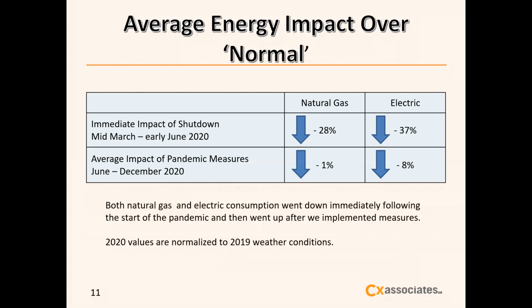I do want to caution us here. The very low energy impact of the measures we implemented for COVID are due to the changes we made and the low occupancy and the lack of events. If we maintain these pandemic sequences when we go back to our much anticipated operating mode of full occupancy and music and plays and weddings, etc., the energy impacts of maintaining the set points of doubled outside air and increased fan speeds for many more hours will be very high.